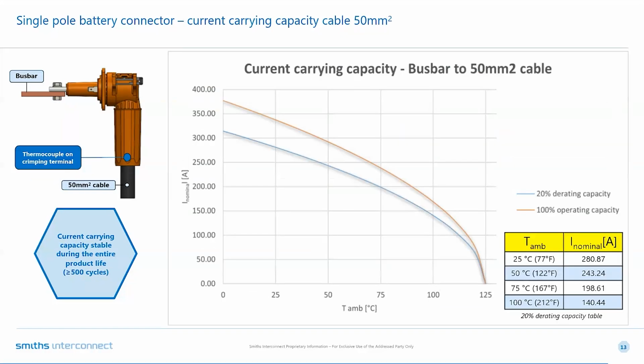The second test presented is the current carrying capacity. The setup shown in the top left image is the same as before, with a change in the measuring system. Now using a thermocouple to measure the temperature increase by applying different current values. In the chart, we present the results of the 300 amp option crimped on a 50 square millimeter cable that is similar to a 0 AWG size.